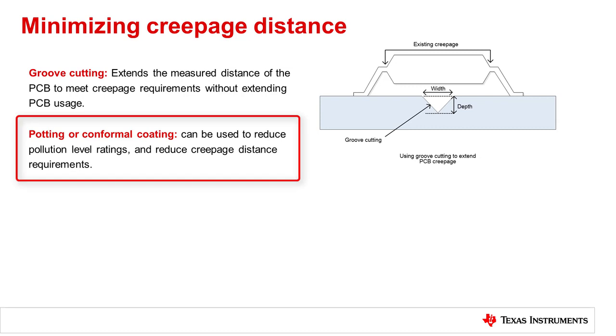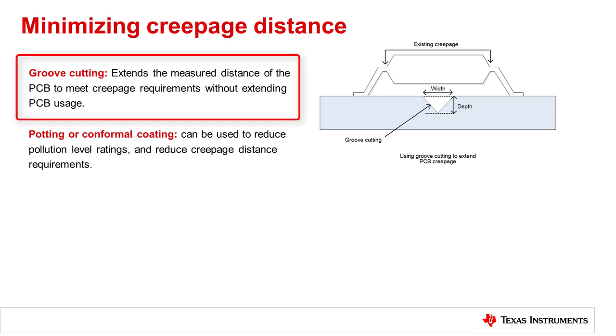There are some techniques that have been used to reduce creepage and clearance requirements. For example, conformal coating or potting techniques involve the deposition of insulating polymer or other material over the printed circuit board and have historically been used to reduce pollution degree around the isolator. This reduces the requirement on creepage and clearance by eliminating the influence of pollutants. Other techniques, such as groove cutting, can be used to attain a lower PCB creepage distance — groove cutting effectively extends the creepage distance.